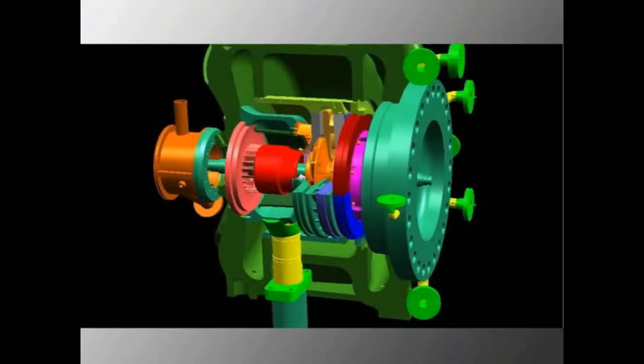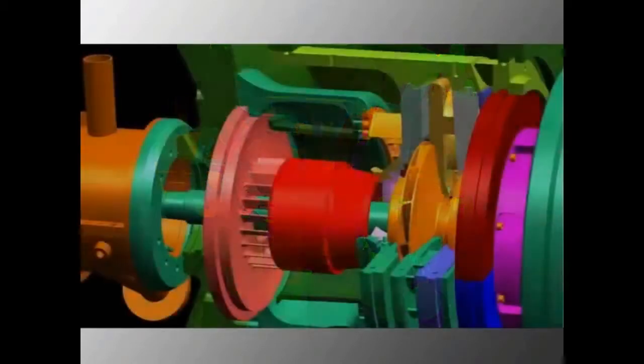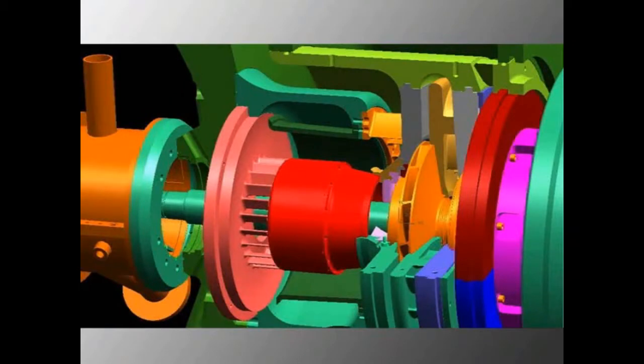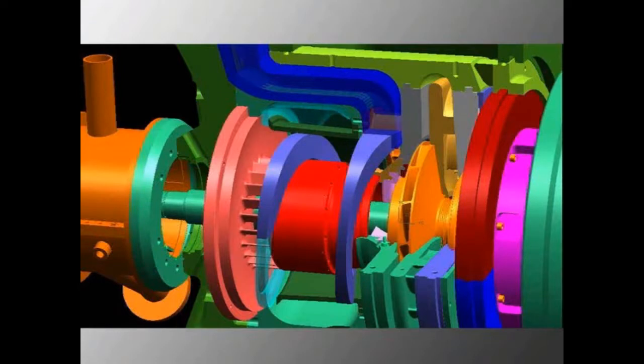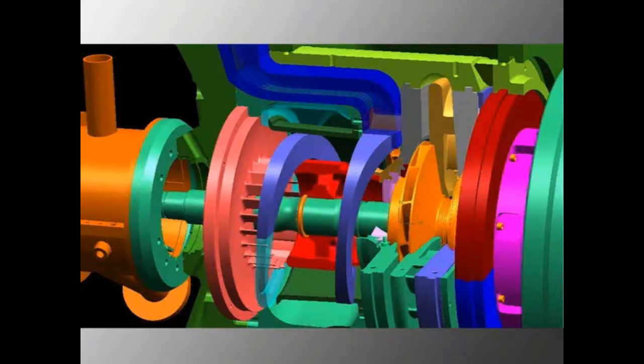The unique advantages over existing technology are evident in this look at the system's centrifugal separator. Fluid enters the compressor intake nozzle and is directed through an initial static separation zone where swirl vanes impart some centrifugal force to the fluids. This allows the bulk liquids to drain off the process gas. The remaining gas is directed through a higher intensity swirl and into a rotating drum. In contrast, conventional solutions use static walls, causing the inevitable re-entrainment of liquids.